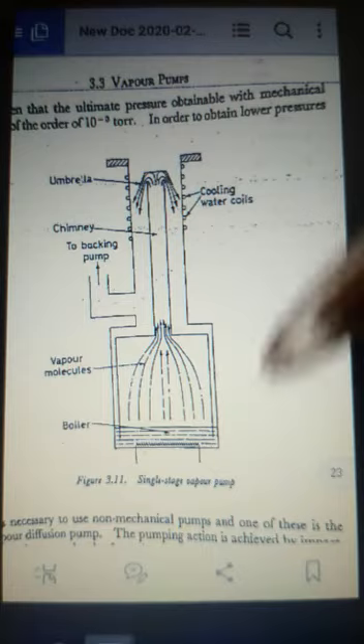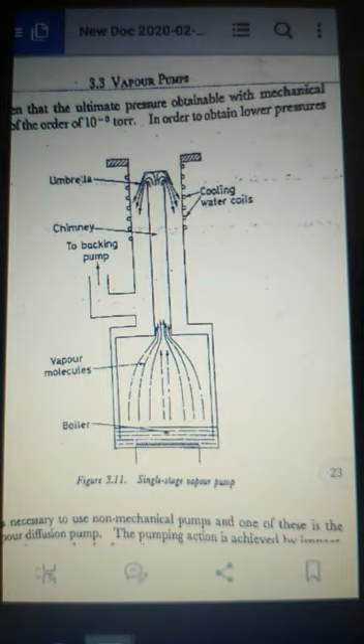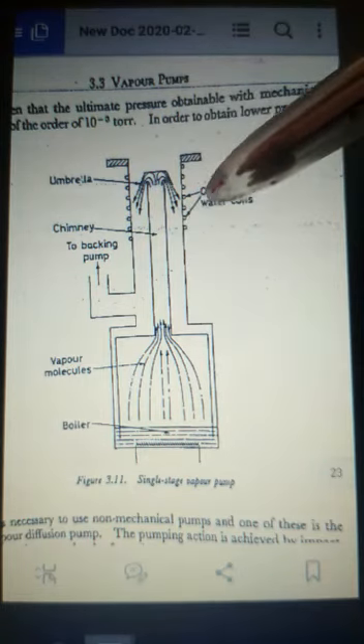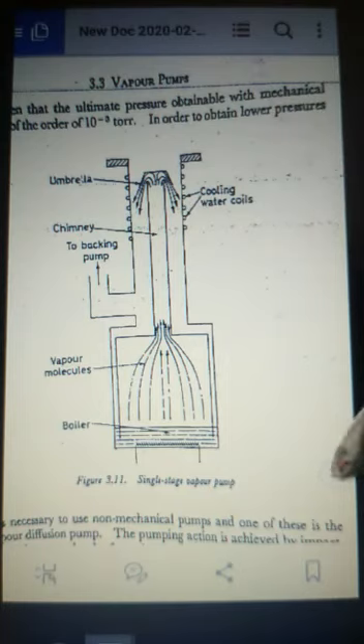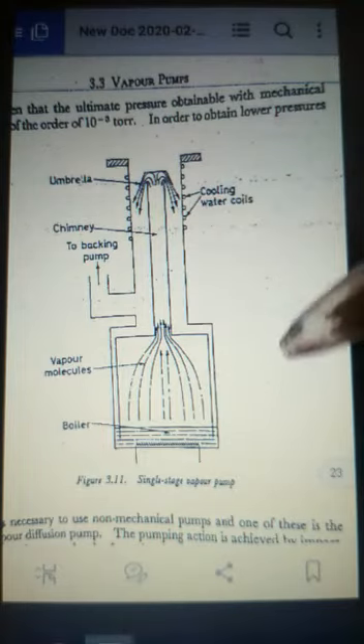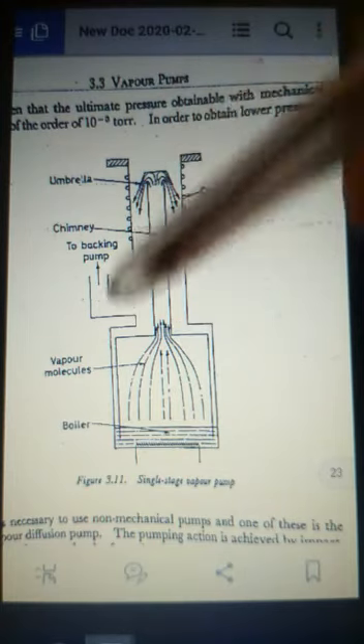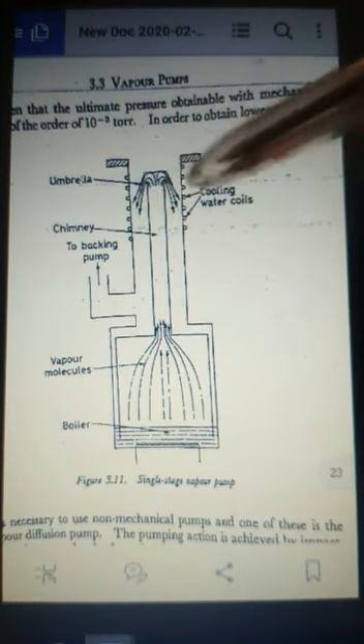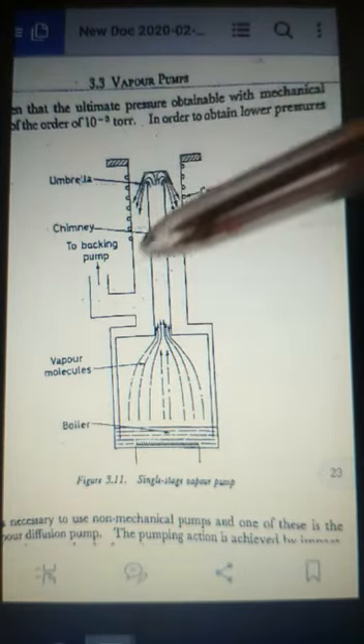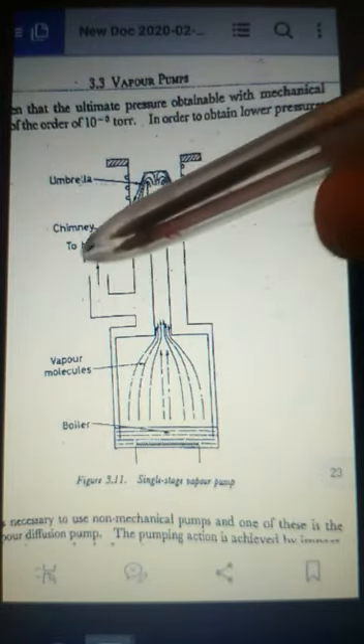The vapor molecules from the boiling fluid travel up in a high speed stream. The gas molecules which enter through the vapor stream gain considerable downward momentum as a result of collision and are swept towards the exhaust. The vapor essentially collides with the cool wall, then condenses to liquid and flows back to the boiler. But the efficiency is very low when we use only one jet.